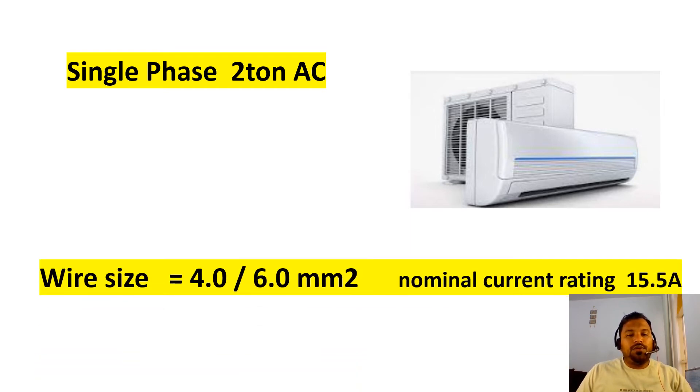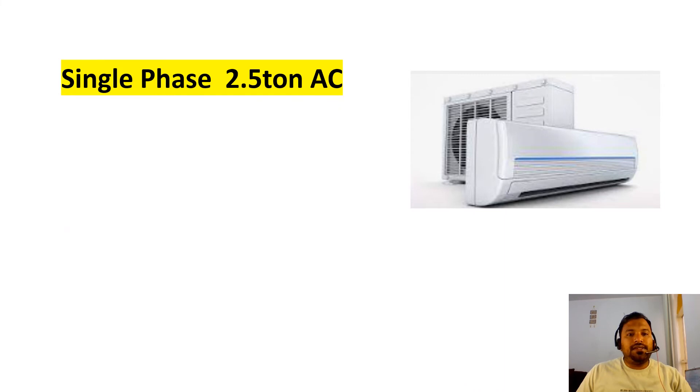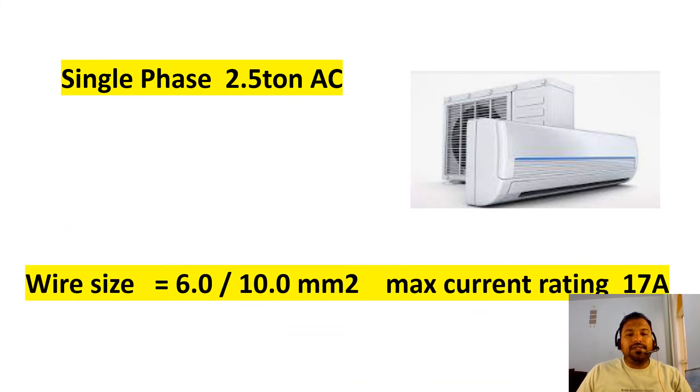For 2.5 ton AC, wire size will be 6 or 10 mm square. So my recommendation, you go with 10 mm square. Why I mention higher wire sizes? Because this 10 mm square is the full rated capacity. This is never operated at full rated, so that is the reason you can go with 6 mm square also.